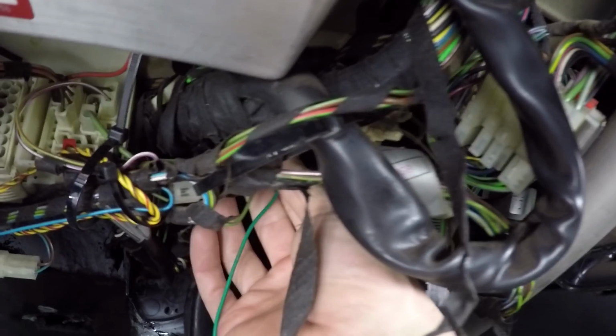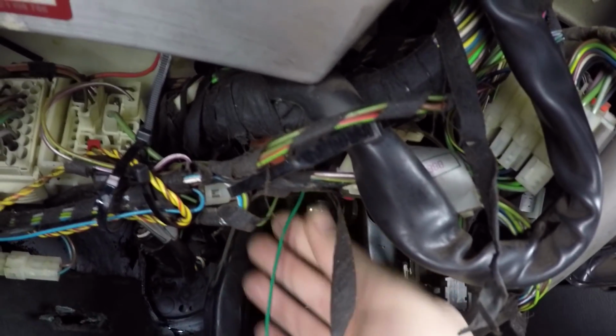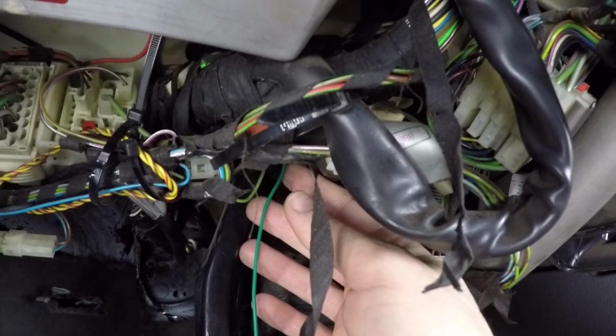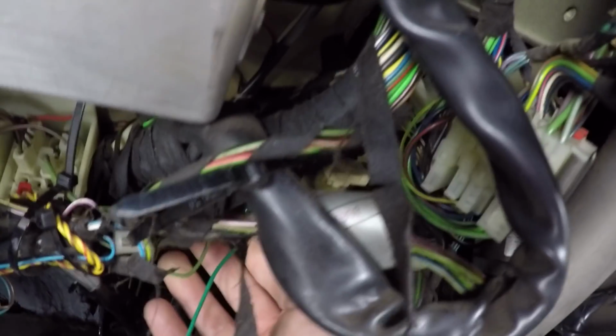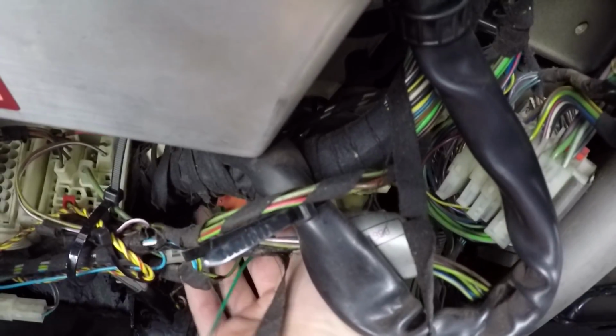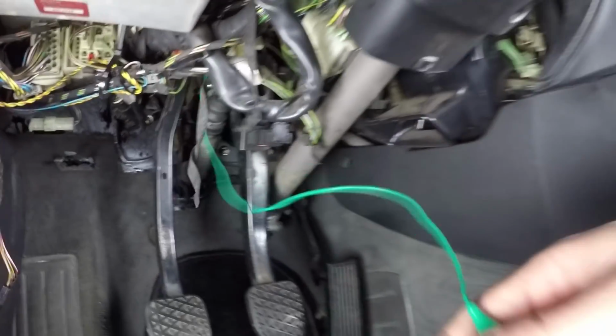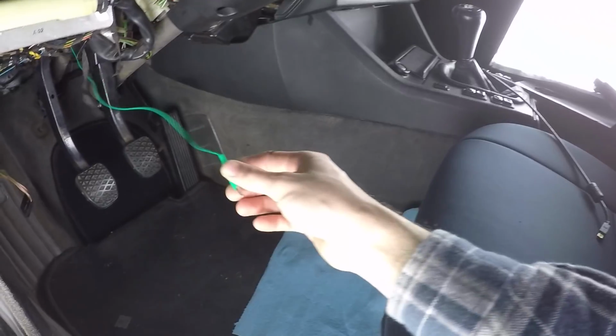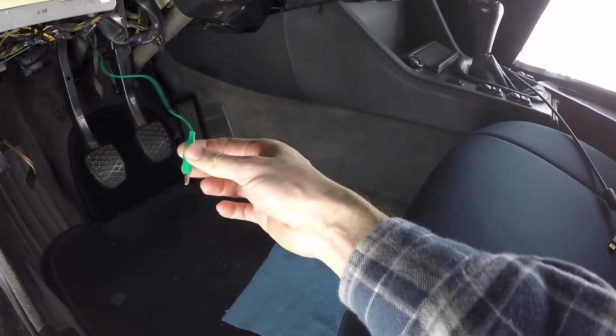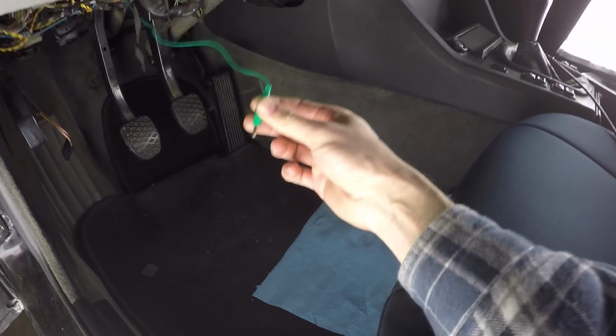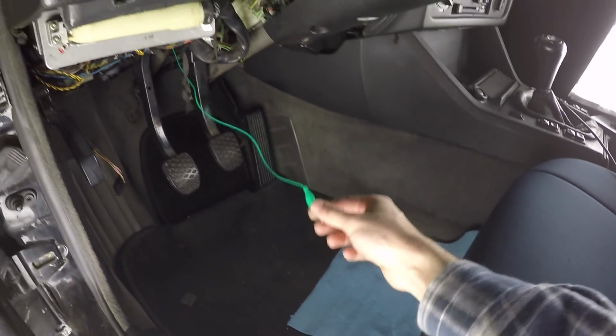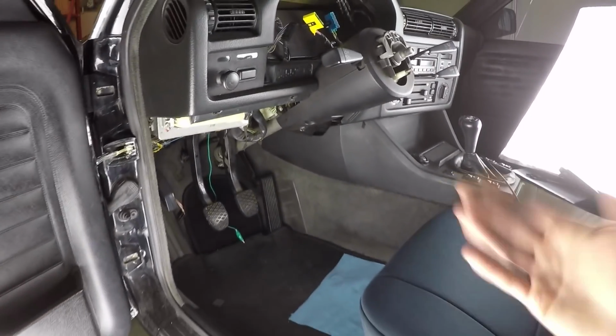And the reason I'm not hooking it up to the bolt or the nut itself that's actual ground is because I want to verify that the wires going to the ground are grounding correctly. So I've just got it clamped to one of the ends of the wires there. With that in place, we've now got our ground for our test equipment. This is how we're going to be making sure we've got a complete circuit when we're testing for voltage at the connectors. So with that there, now it's time to get our positive side hooked up.